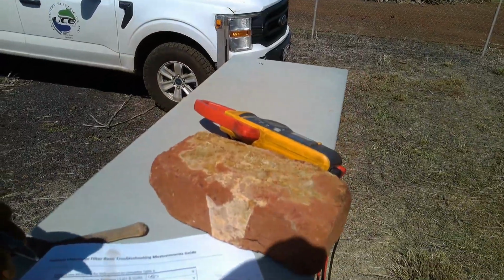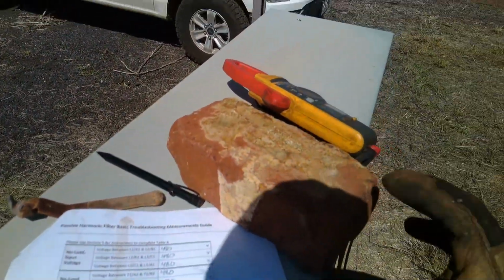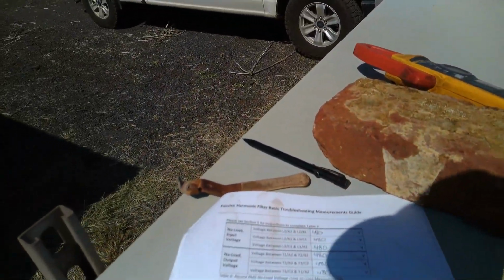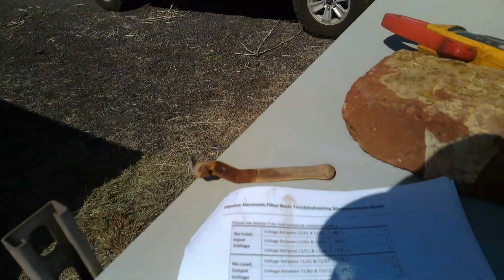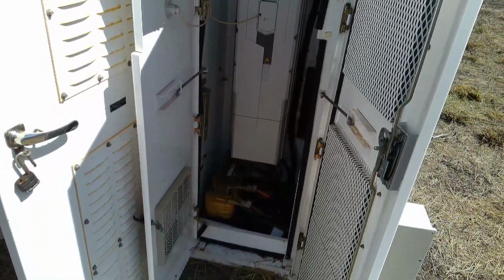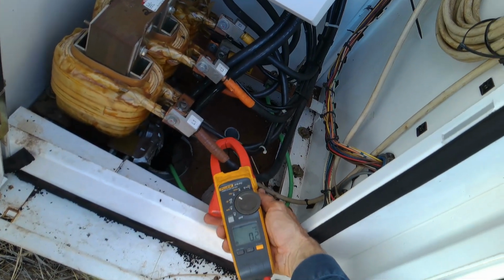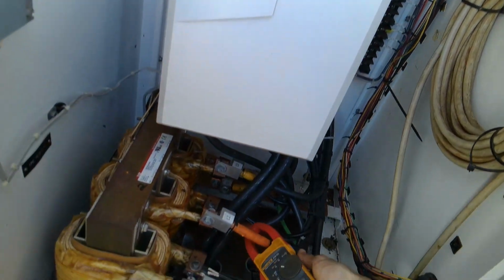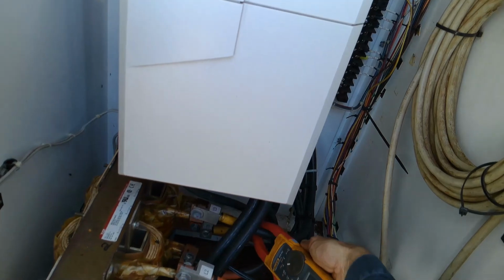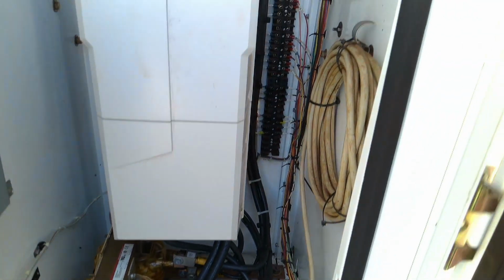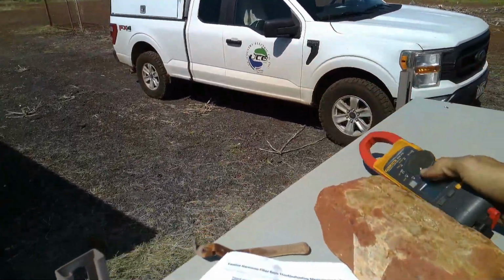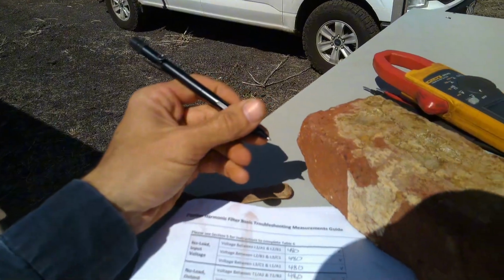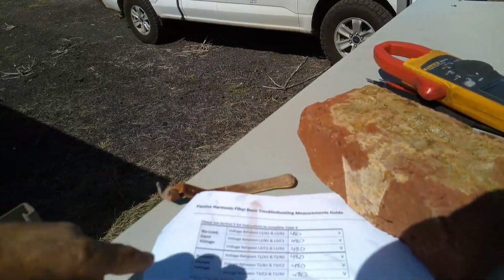Then they want current. Section 5, where do they want the current from? Current on the input wires to the line reactor with no load. Okay? Essentially 0, 0.2, 0.3. I need to engage the contactor. Okay.